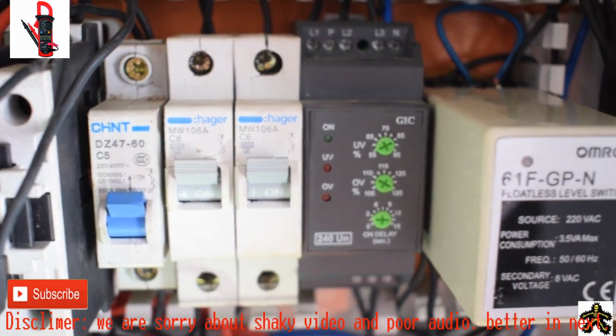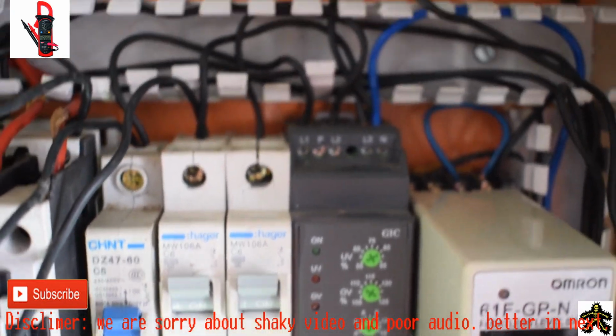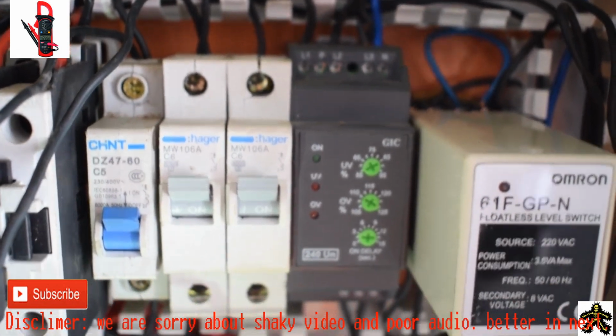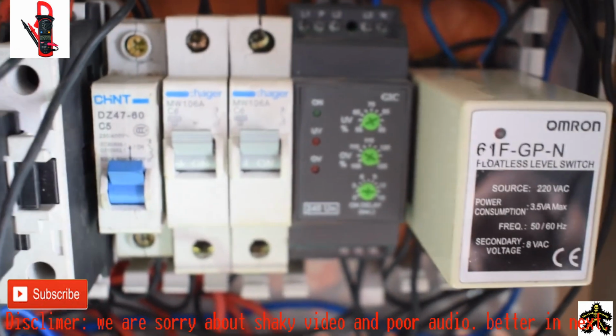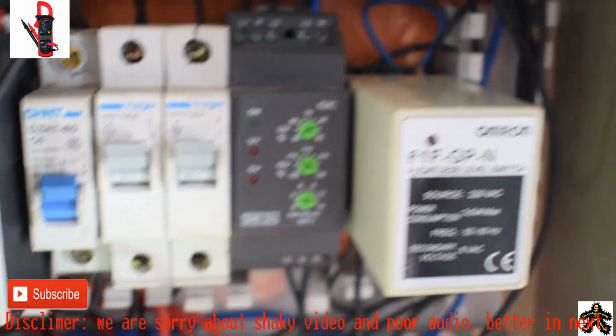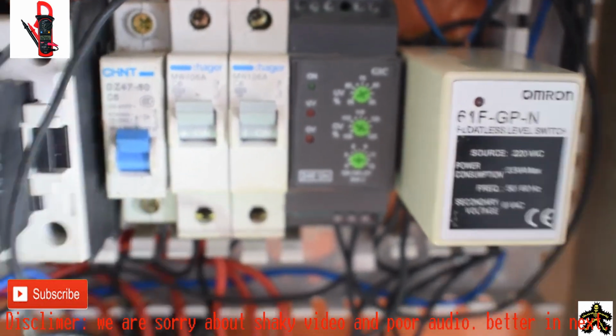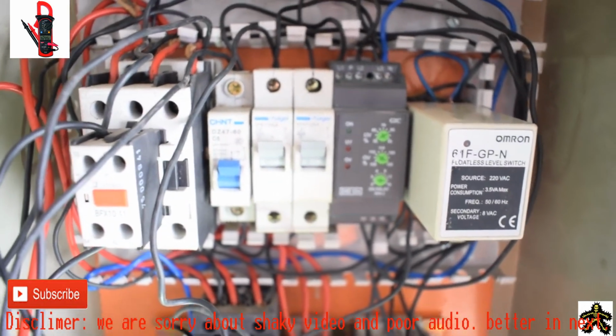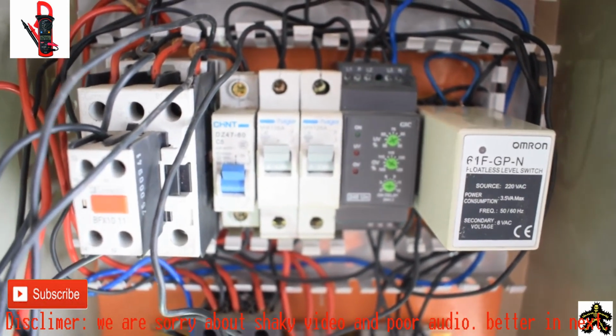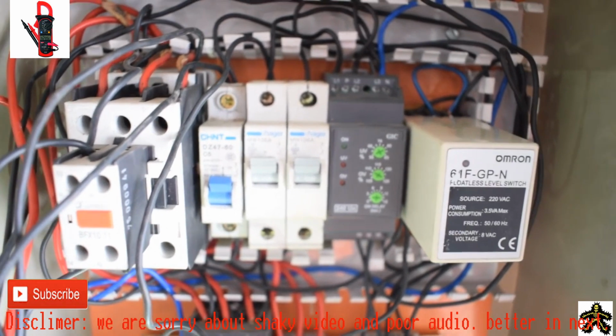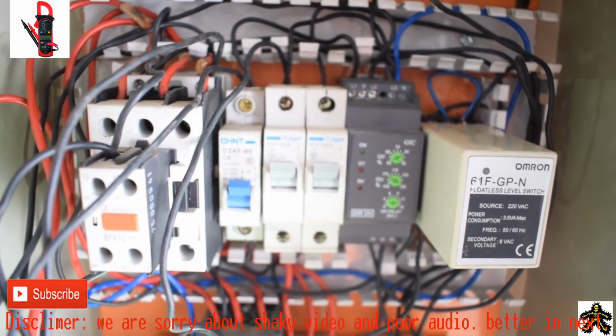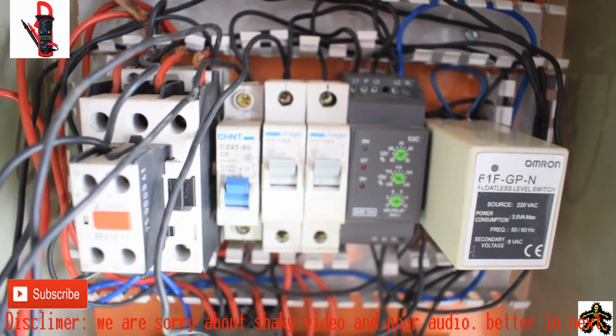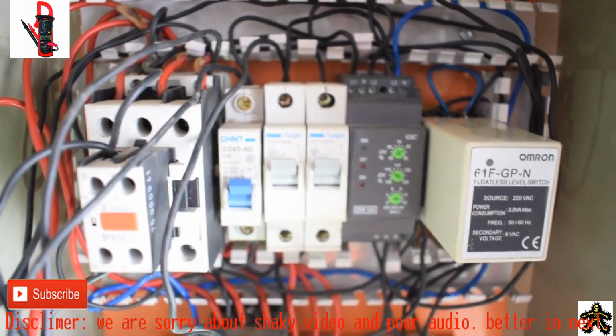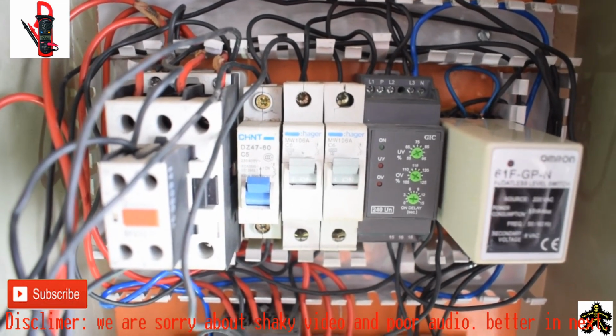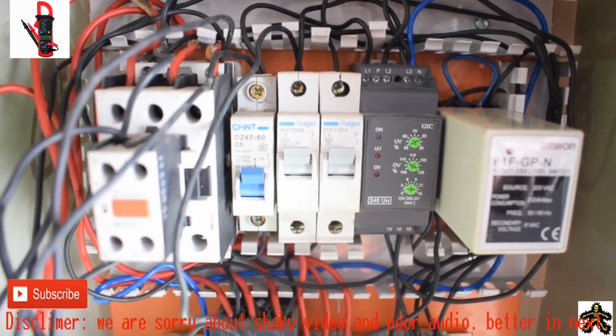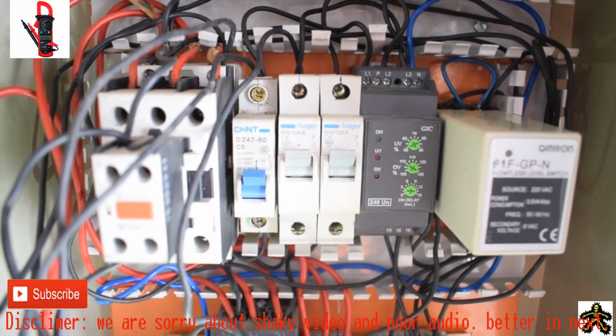Now, the reason I brought you to this box is that I wanted to show you what a typical phase failure device looks like. This box was initially a changeover, a pump control. If you look critically there, you see we have a three-phase contactor, three breakers, a phase monitor and a float switch. But right now our focus is on the phase monitor, how it controls the circuit and how it helps the motors work normally without any worry of burning.